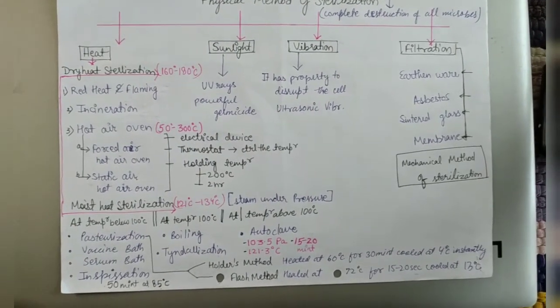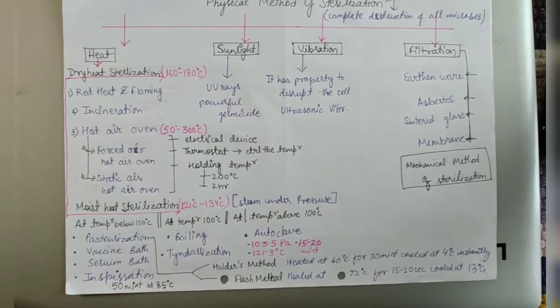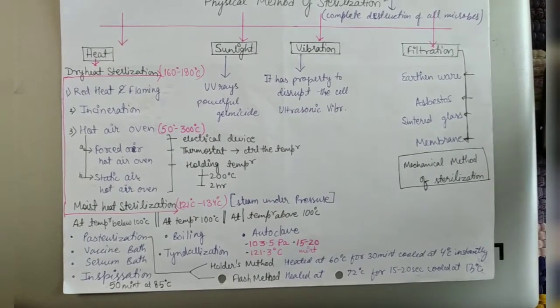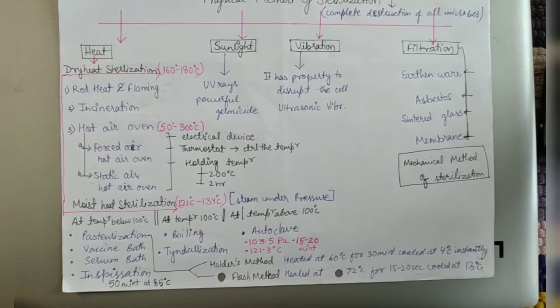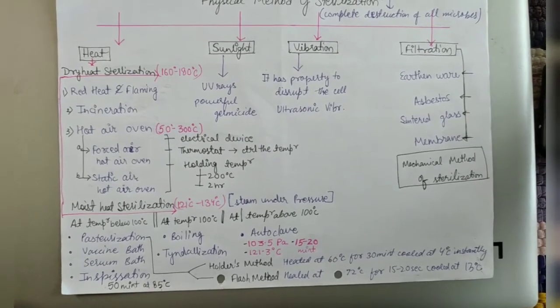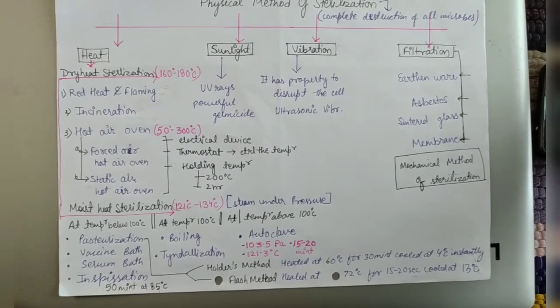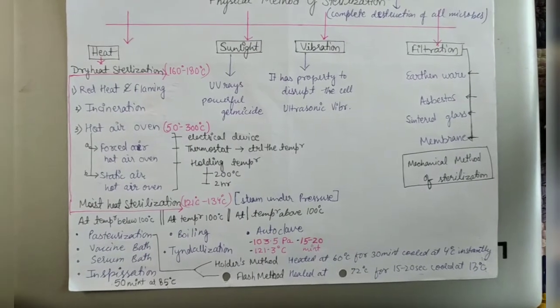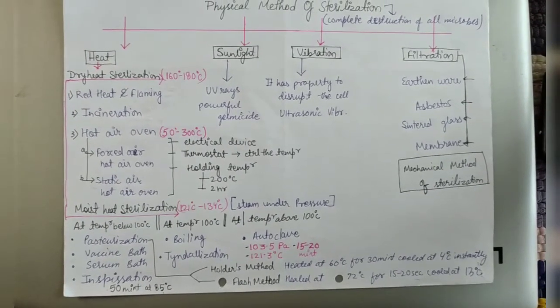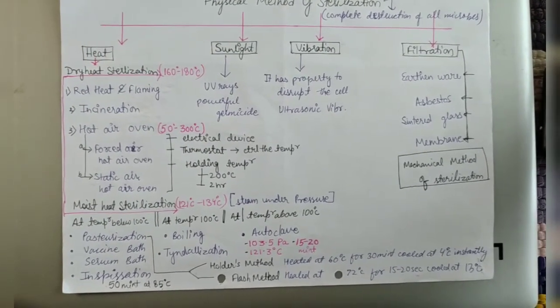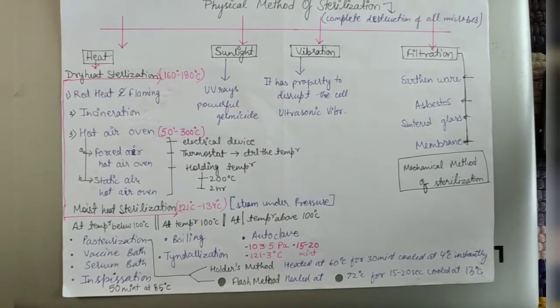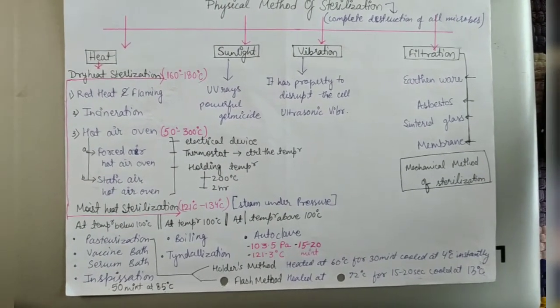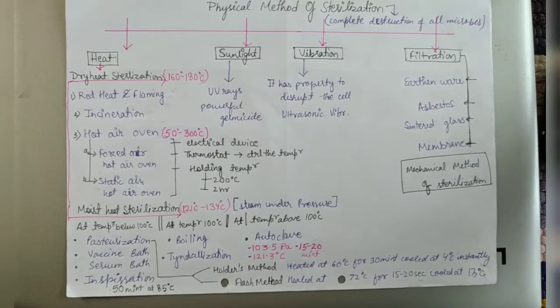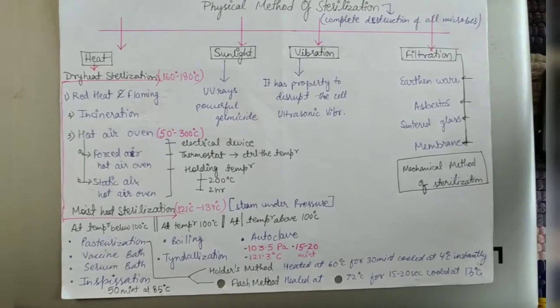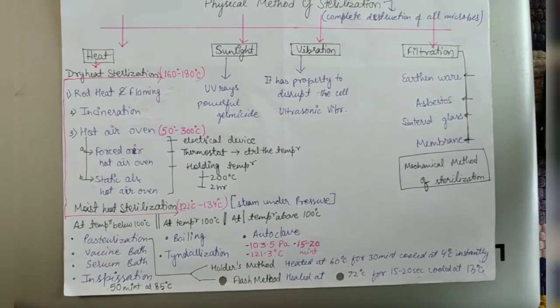Then hot air oven. We have two types of hot air oven: forced air hot air oven and static air hot air oven. We require a temperature from 50 degrees Celsius to 300 degrees Celsius. And hot air oven is an electrical device. उसमें thermostat present होता है, means we can control the temperature whenever we want. The recommended temperature for sterilization in hot air oven is 200 degrees Celsius for 2 hours.